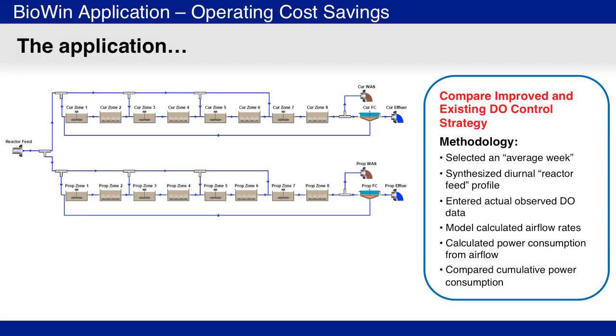The plant also had information on power consumption as a function of air flow, so it was possible to compare predicted versus observed power consumption. Once the model was calibrated and predictive of the plant behavior, it was applied to investigate the alternative dissolved oxygen control strategy. To facilitate comparisons between the current and proposed control modes, the following approach was used.